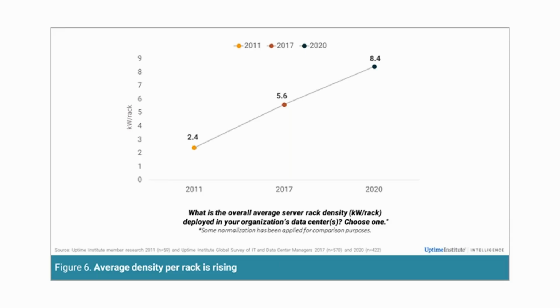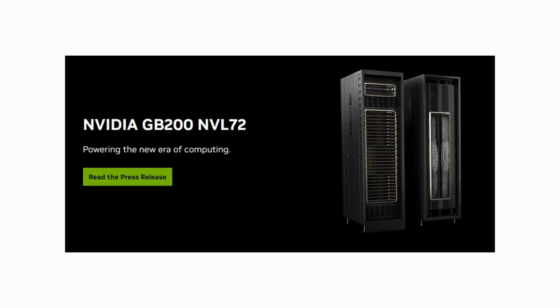But as we're all aware, the last 5 years, things have gone absolutely bonkers in this space and created a lot of challenges that we need to be addressing inside of our data centers. So what was the big turning point? Obviously, NVIDIA is leading the way as a disruptor in this space with their computing power. The GB200 produces over 120 kW per rack, and there's some versions of this that produce over 130 kW per rack. Keep in mind that the NVL72 means there's 72 individual chips inside of that rack, each of them putting off a tremendous amount of heat, and we're generating more heat than we've ever seen before.